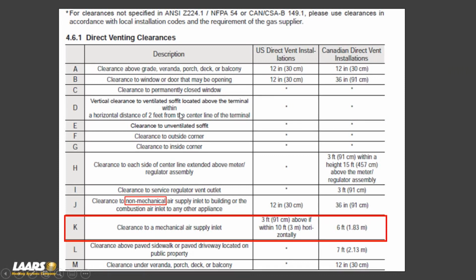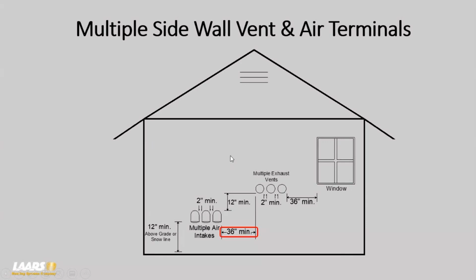Now, the National Fuel Code, NFPA 54, a lot of people try and go by line item J, clearance to non-mechanical air supply inlet to a building, or combustion air inlet to another appliance. However, that's non-mechanical, and it talks about 12 inches. If you've got multiple pieces of equipment, your clearance to a mechanical air inlet supply should be 3 feet. This drawing actually came out of our Neotherm manual. If you've got multiple appliances, your separation for exhaust to combustion air should be a minimum of 3 feet.